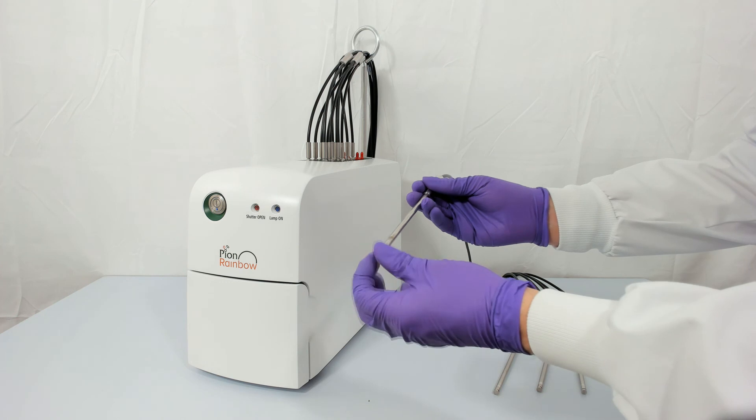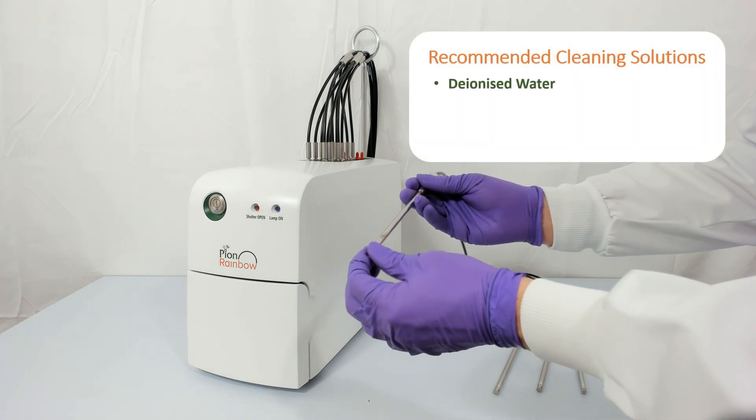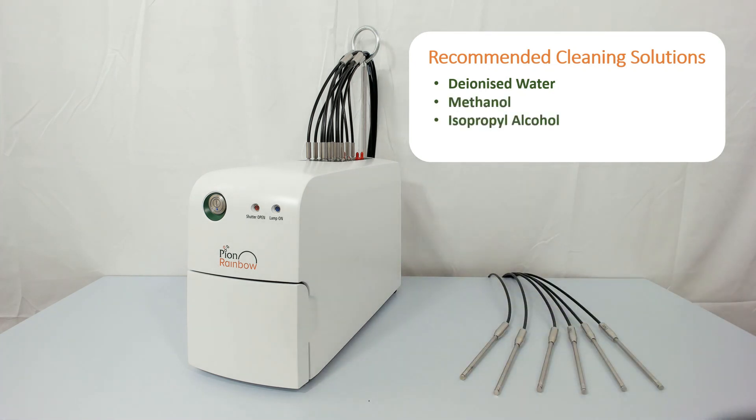The probes and tips are broadly compatible with the majority of common laboratory reagents. We recommend deionised water, methanol or isopropyl alcohol for general purpose cleaning, or DMSO for very stubborn contaminants.